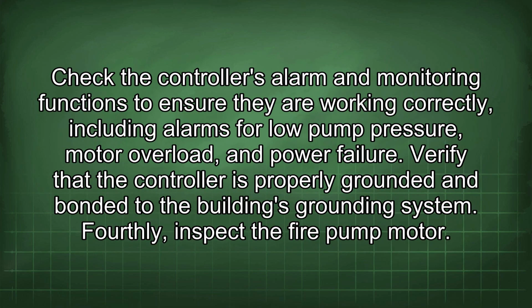Check the controller's alarm and monitoring functions to ensure they are working correctly, including alarms for low pump pressure, motor overload, and power failure. Verify that the controller is properly grounded and bonded to the building's grounding system. Fourthly, inspect the fire pump motor.